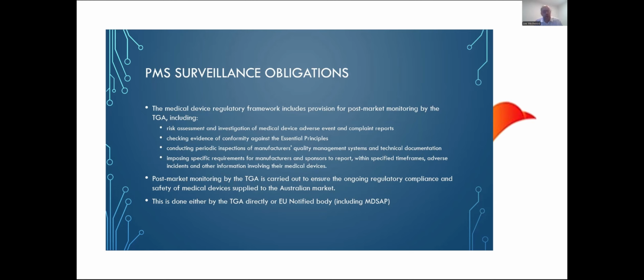Once you've got your device approved and on the ARTG database, and your device is ready to go, the post-market surveillance of the TGA kicks in. Similar to the European Union, you don't just get your device on the market and then forget about it. The TGA will carry out inspections to ensure that clinical evidence is being kept up to date and is still in compliance with the essential principles. They can inspect the quality management system. This can be done directly by the TGA or through an EU notified body, depending on which manufacturer evidence you've supplied relating to your quality management system. But this is where the MDSAP certificate has a lot of merit, because it covers the TGA requirements and will most likely prevent the TGA from coming to your facility.